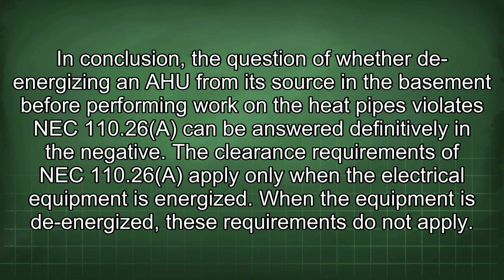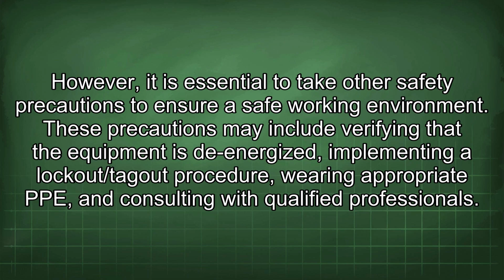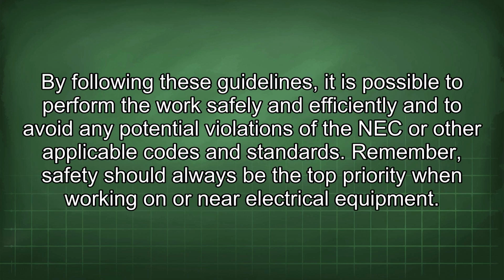In conclusion, the question of whether de-energizing an AHU from its source in the basement before performing work on the heat pipes violates NEC 110.26 can be answered definitively in the negative. The clearance requirements of NEC 110.26 apply only when the electrical equipment is energized. When the equipment is de-energized, these requirements do not apply. However, it is essential to take other safety precautions to ensure a safe working environment. These precautions may include verifying that the equipment is de-energized, implementing a lockout/tagout procedure, wearing appropriate PPE, and consulting with qualified professionals. By following these guidelines, it is possible to perform the work safely and efficiently and to avoid any potential violations of the NEC or other applicable codes and standards. Remember, safety should always be the top priority when working on or near electrical equipment.